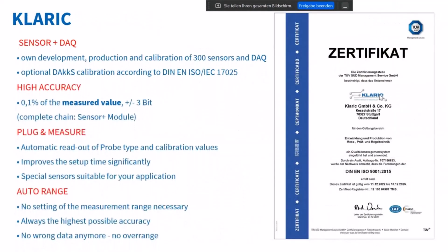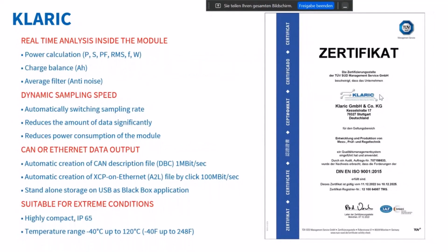So this is the overview: we have our own calibrated sensor and data acquisition system, with high accuracy of 0.1% from the measured value, plug and measure technology, auto range, very easy to use. We can also analyze the data inside the module - we have a power analyzer built in, and we can calculate power, apparent power, power factor, cosine phi, RMS value, frequency for AC, and so on.